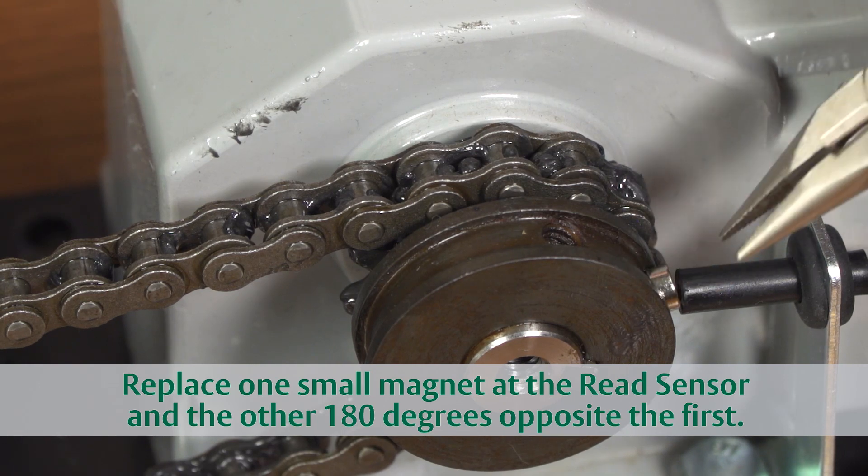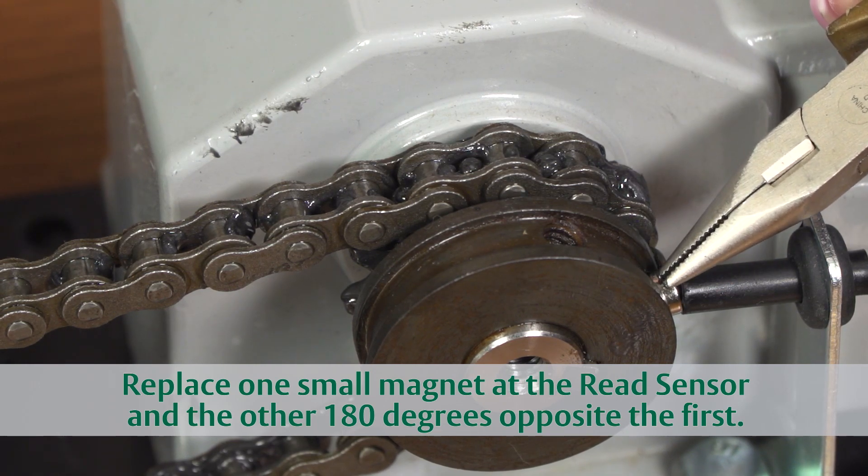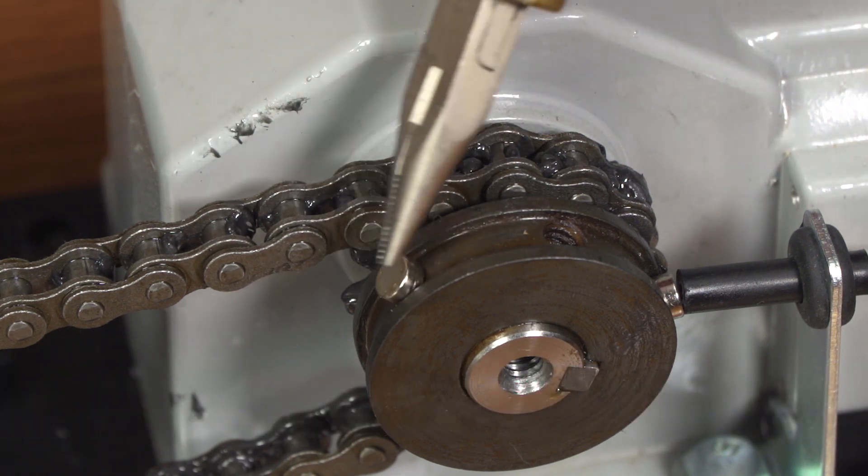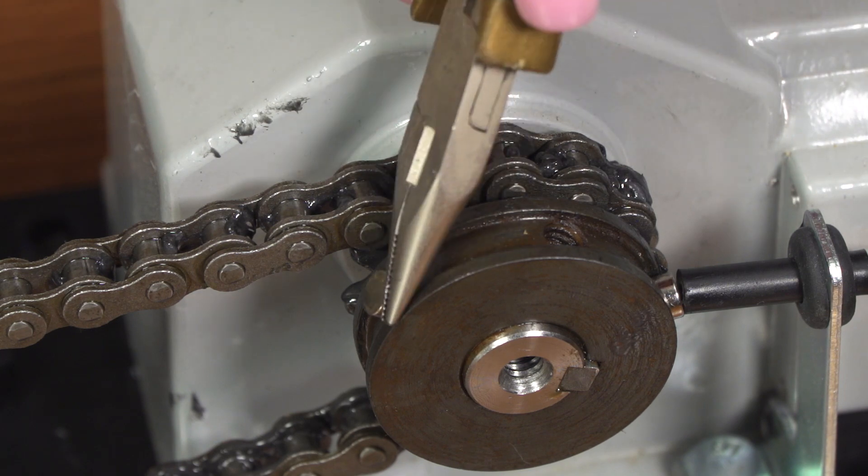Now, replace both magnets into the motor sprocket. Be sure one of the magnets lines up with the reed switch. This sets the closed position. The other open position magnet should be approximately 180 degrees from the first.